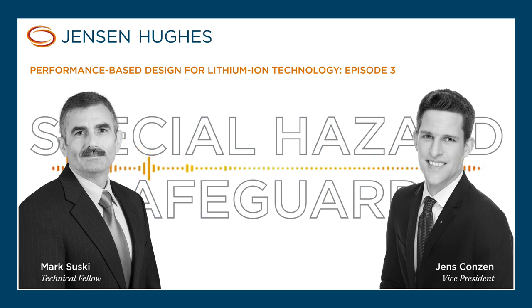In the EV manufacturing area, some of the areas we're most interested in currently are the formation where they're charging, the aging, and the testing areas. Now they've determined that 30% state of charge is no longer sufficient to determine if there are actually defects within the cell, so they're starting to charge the cells higher—up to about 62% state of charge now. For years, the industry said under 30 we're good, no problem—it's kind of an inert battery, not a big deal. But now we're charging that battery up to 62%, so there's research and studies being done on how that's going to affect the overall fire, protection, and life safety.